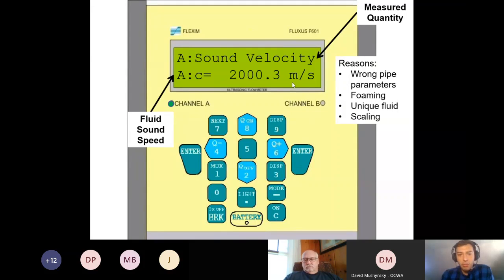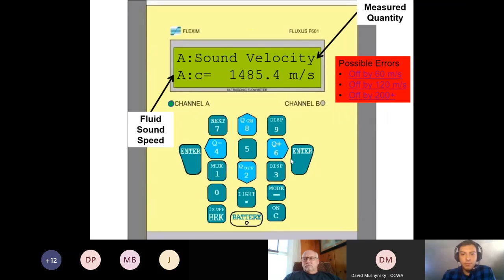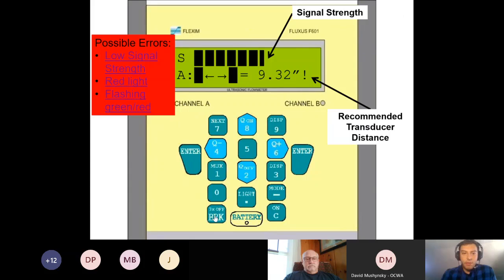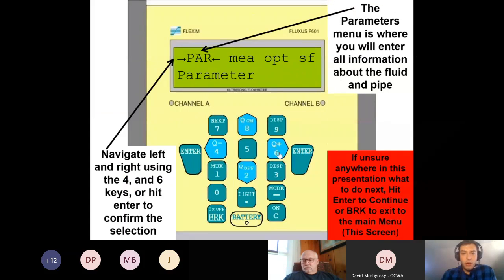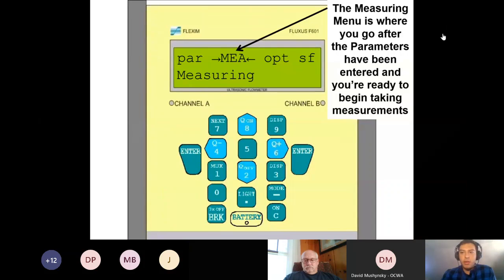It could also be foaming in the pipe, or the transducers just not communicating with each other. If you have this high sound speed and you have a red light, that's the transducers not communicating with each other, and it's just the ultrasonic beam bouncing back and forth a lot inside of the pipe. So definitely go back and check, make sure you have everything plugged into the parameters properly if you have that off of a sound speed. And for the most part, that is how you program a meter, measure with it, and troubleshoot it. I'll now open it up to any questions.